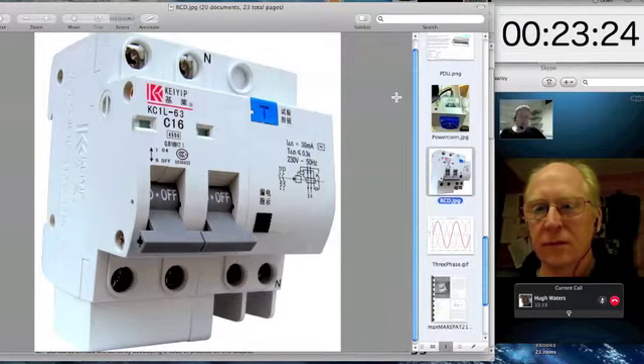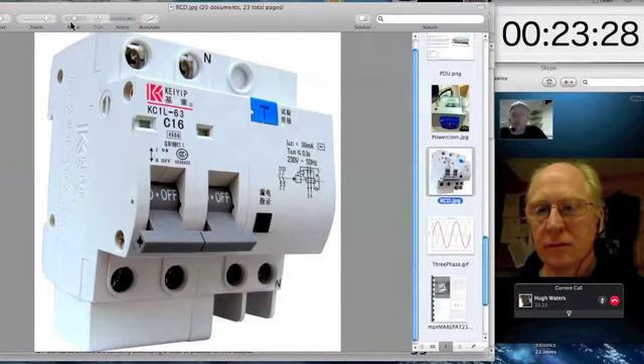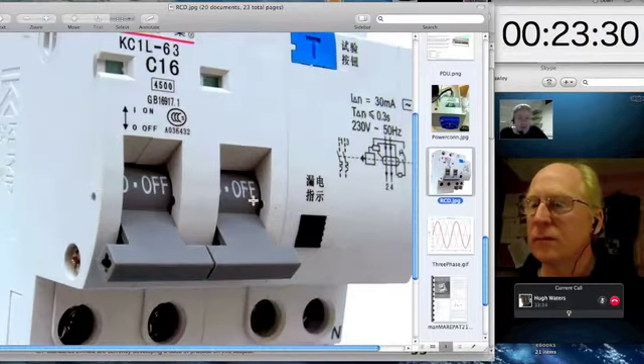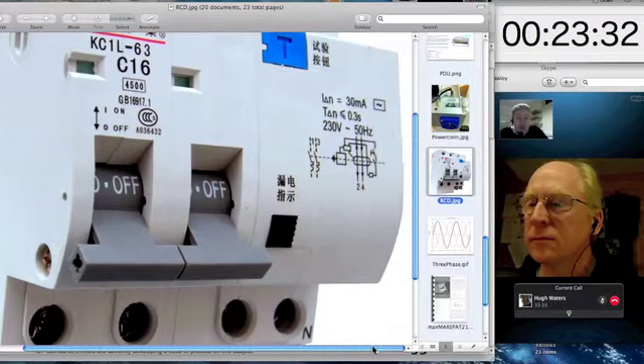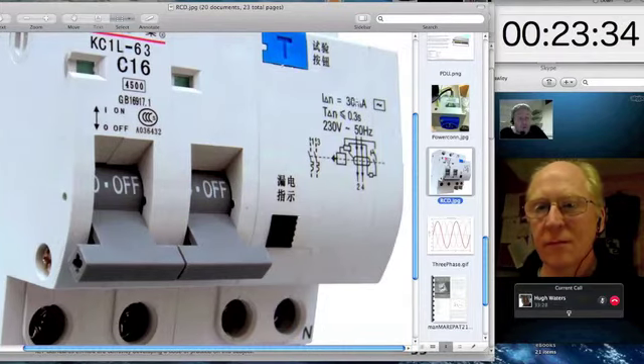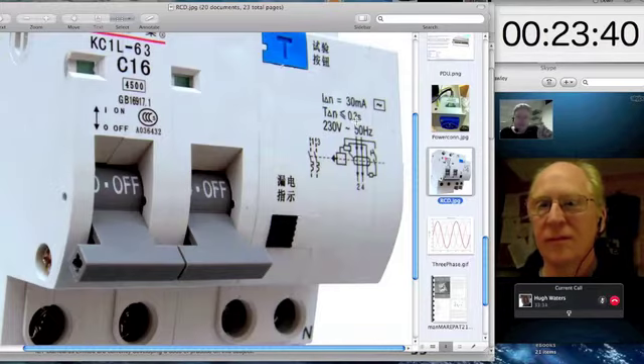the neutral supply. And if there's more than just about, well, in the case of this one I've got up on the screen at the moment, I'll zoom in so it's even clearer. If there's more than 30 milliamps of difference between the live and the neutral, you've got to say to yourself, where's that current going? We're sending a different amount of current down one leg than is coming back up the other leg. Where's that current going? Is it travelling through some poor person's body to earth? Yes. And if it is, we better break this circuit. We better interrupt the flow.